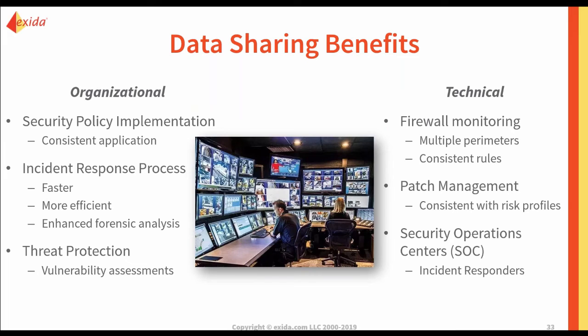And there may be other aspects that have to do with patches and patch management. IT and OT have a fundamental disagreement there, because IT would often say, we'll just reboot the server, new patches installed, life goes on. But OT, having long-running processes, may not be able to take something down. So the scheduling of patches within a maintenance window can become important, and making sure those things are done during certain time windows when you're able to maybe take a plant offline.